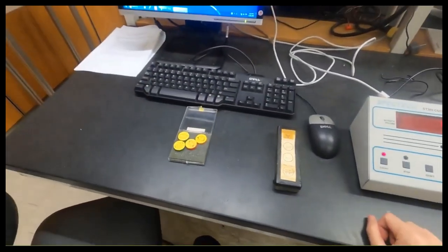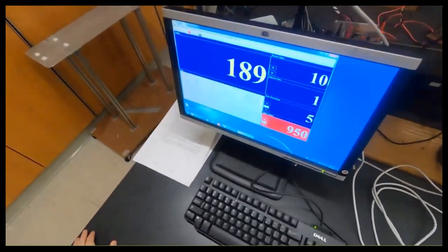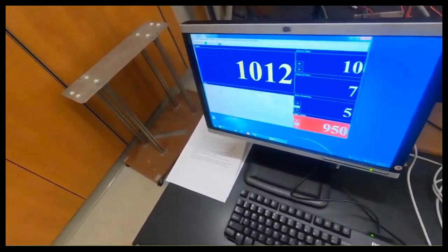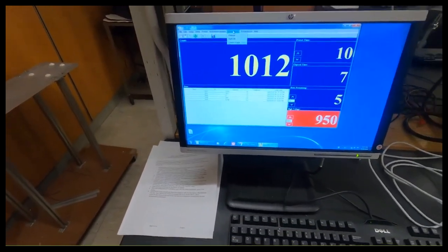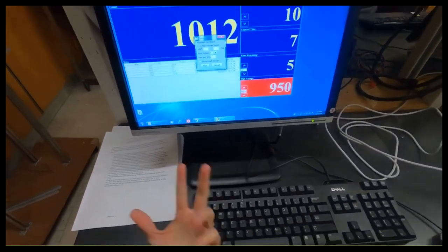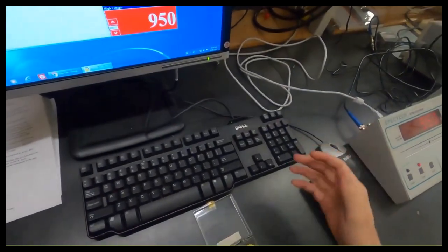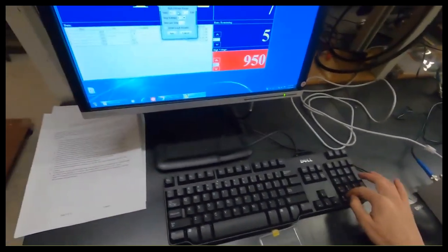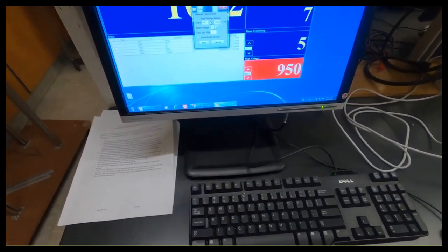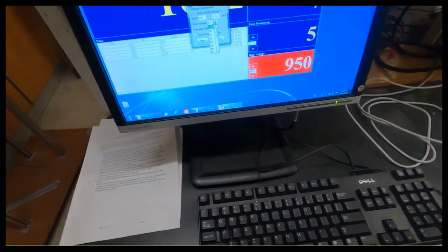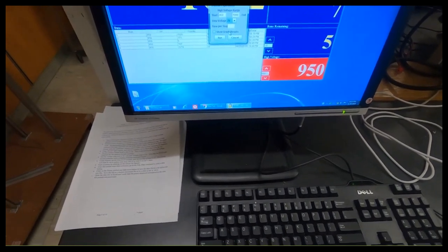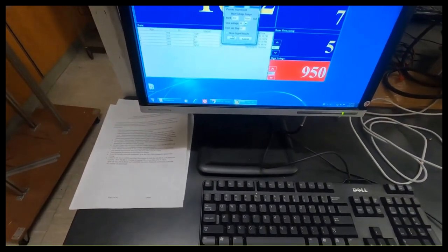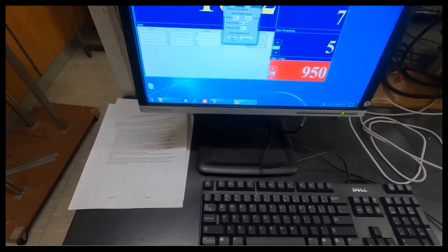Okay, so the first experiment you do is a plateau experiment. All measurements you perform should be done in the plateau. So you can select right here, experiments, plateau, and here you can input your parameters. So for example, you can start from 400 volts, and you can end at 1000 volts. Never exceed this voltage. And the step voltage can be 20 volts. And you can select, for example, 20 seconds for each time. And if you check this box, you can see the results, and then you can run.